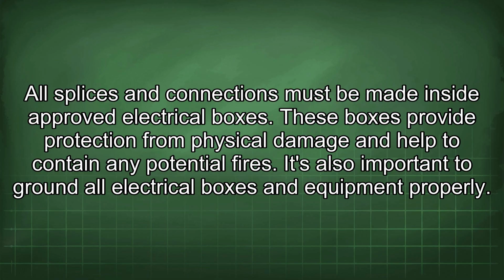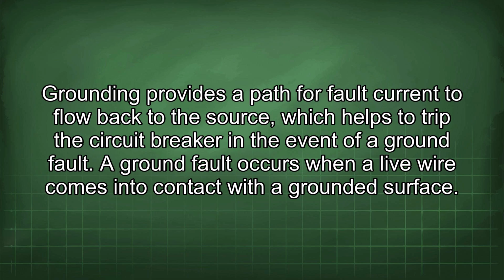It's also important to ground all electrical boxes and equipment properly. Grounding provides a path for fault current to flow back to the source, which helps to trip the circuit breaker in the event of a ground fault. A ground fault occurs when a live wire comes into contact with a grounded surface.